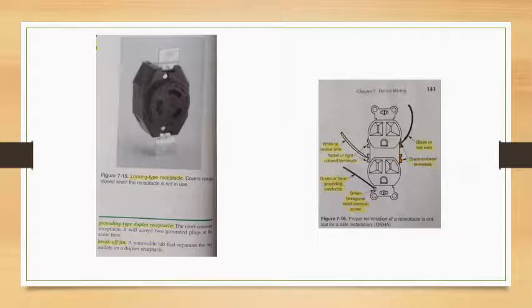Grounding the receptacle. Methods of grounding the receptacles vary. The method selected depends on the type of wiring system and boxes used. In a metal conduit system, the conduit and metal boxes provide the proper equipment ground all the way back to the service entrance panel. In this case, there is no need for a grounding conductor. When the receptacle is attached to the box, grounding contact is made through the receptacle yoke and screws to the box. In addition, local codes may require a bonding jumper to be installed between the receptacle grounding screw and the metal box. Other wiring systems requiring a ground include armored cable or BX, flexible metal conduit or greenfield, non-metallic cable, and rigid plastic conduit. There must be continuity from the grounding screw of the receptacle to the ground wire and to the metal box if present.